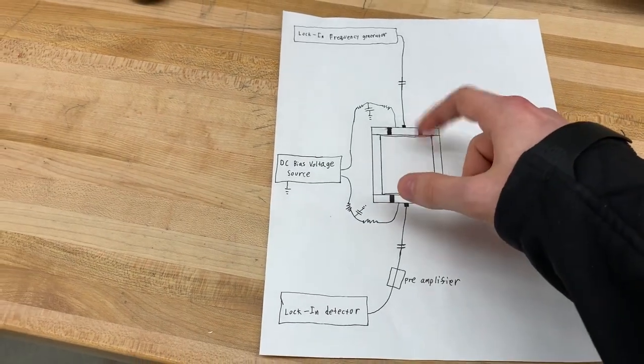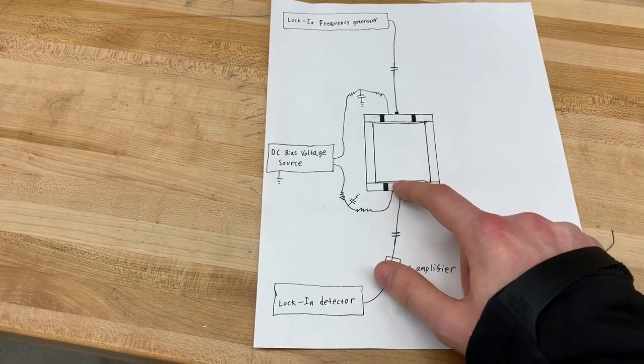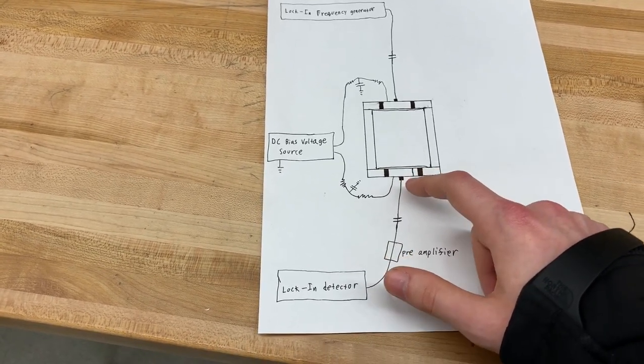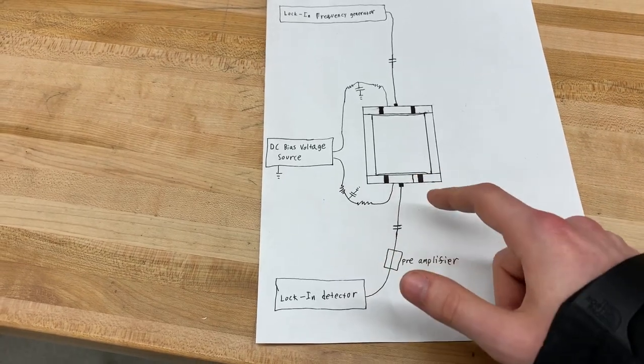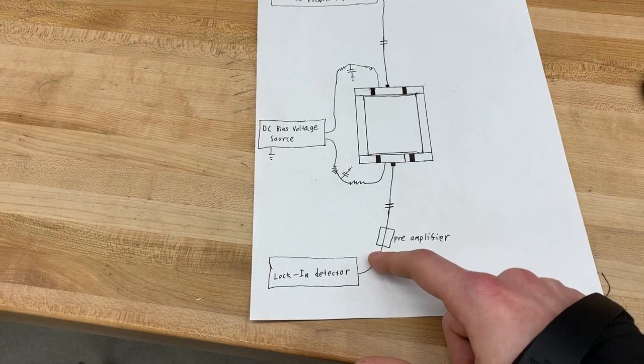I actually said this one was the driver, so that's what will be happening there. Now if we're looking at the detector one, the sound will move that membrane back and forth, and that will create an oscillating current, because it's charged, and that's also charged here, which will then be detected. We have a pre-amplifier there.